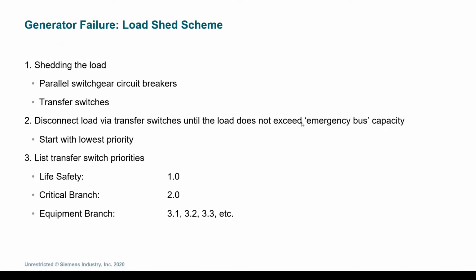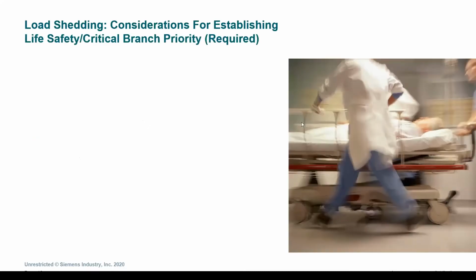Earlier, we mentioned that it's important that the transfer switches and the generators can support all of the priority 1 and priority 2 loads, meaning, as shown here, the life safety and the critical loads. In the event that, say for instance, in the example, all the generators fail except one of the smallest ones that cannot fully support that load, it is still important in best practice, although it can never be done except when generators fail, that all of the transfer switches still have a priority designated to each of them. So again, when we look at what this means from a facility and identifying a proposed priority, life safety, priority 1.